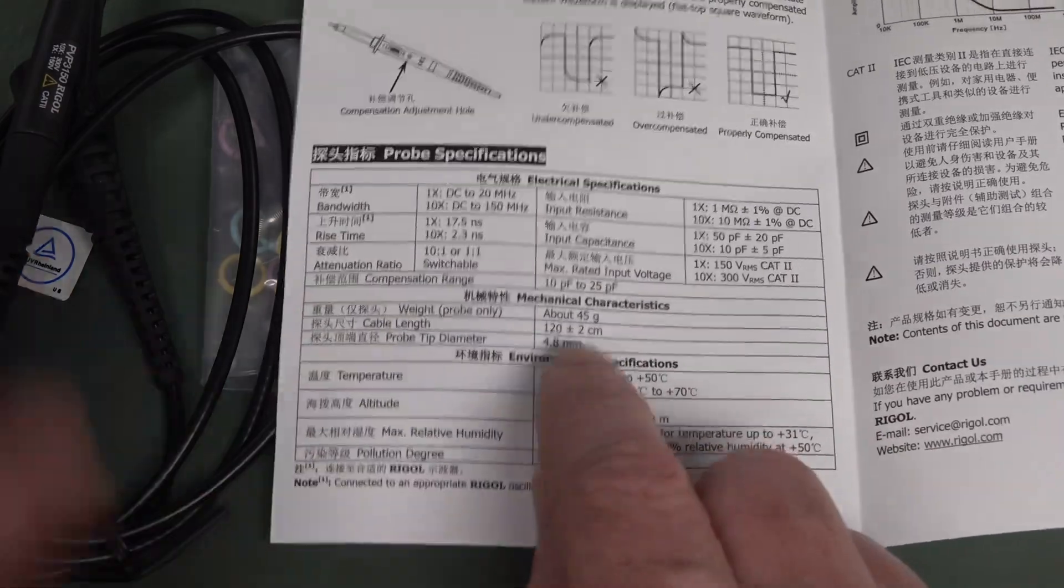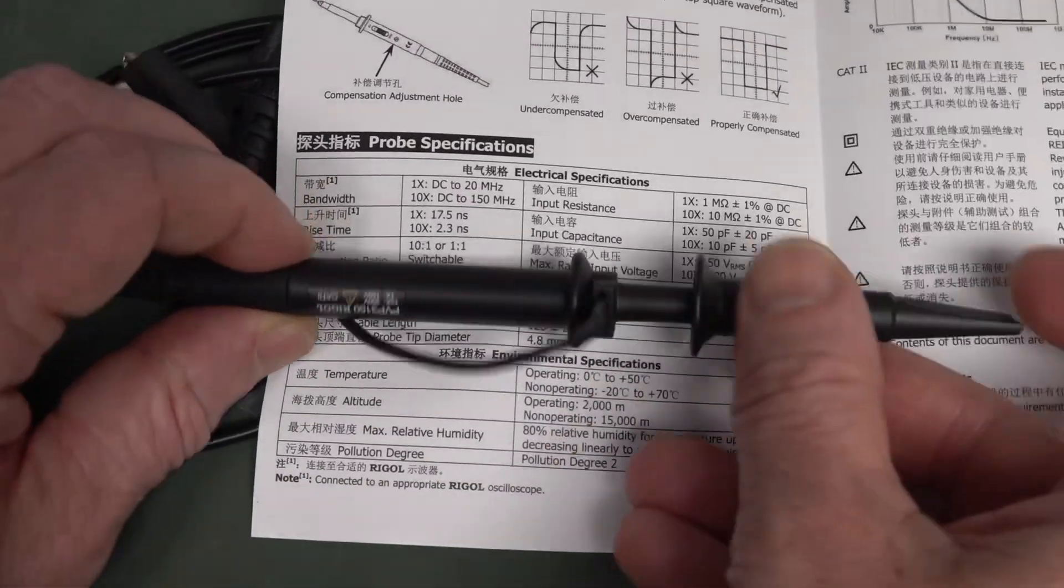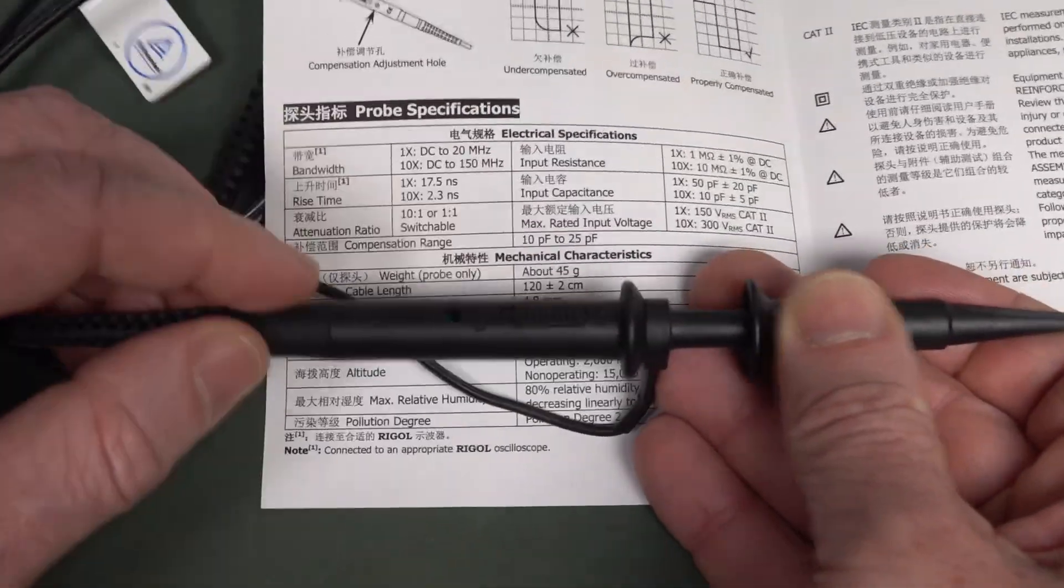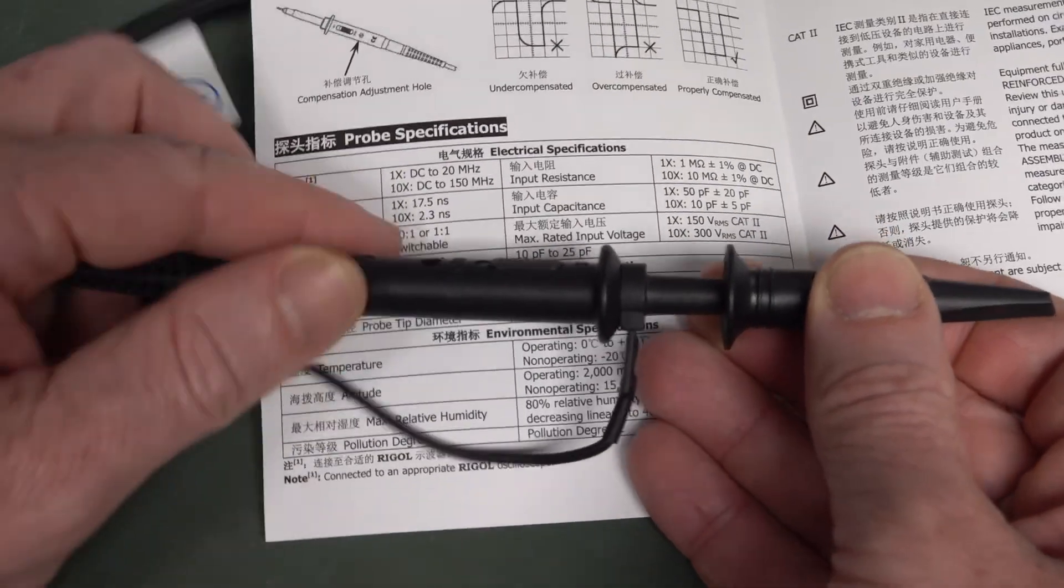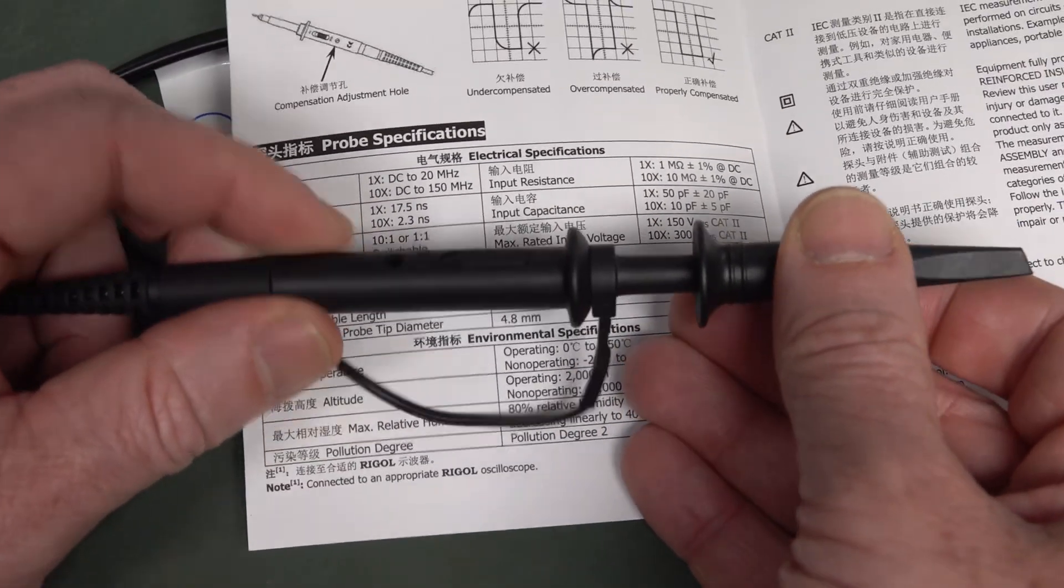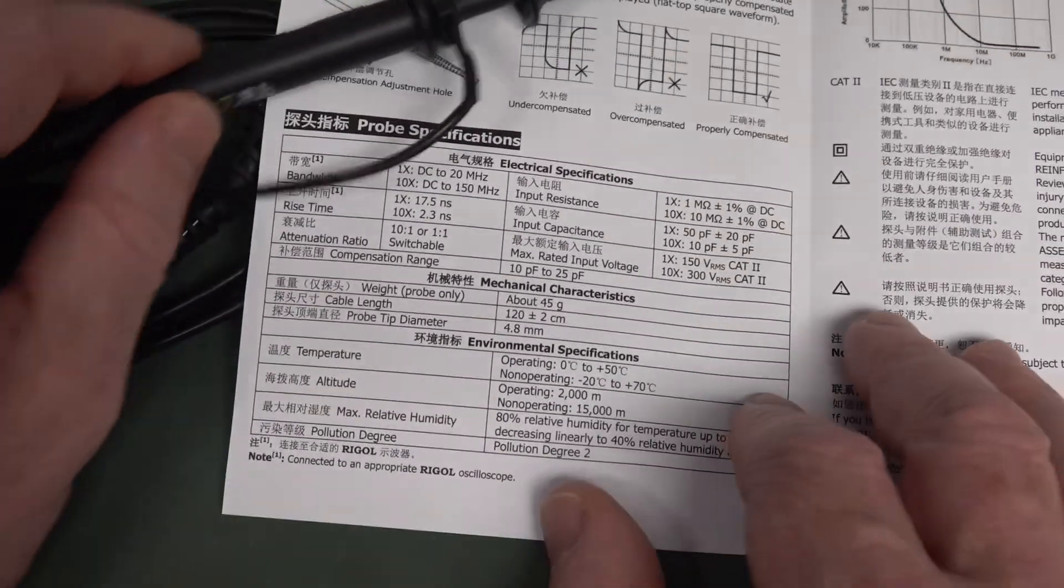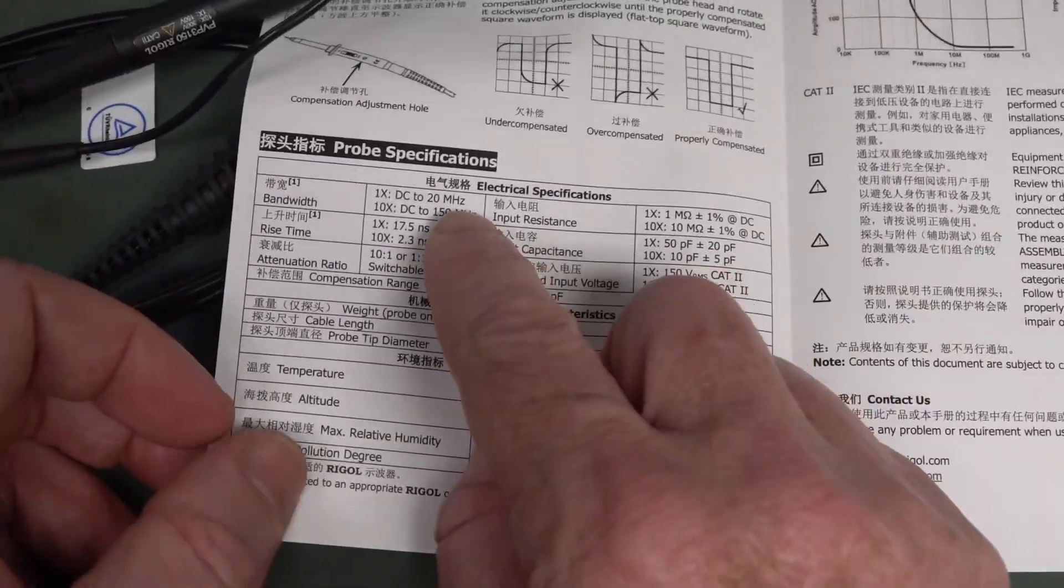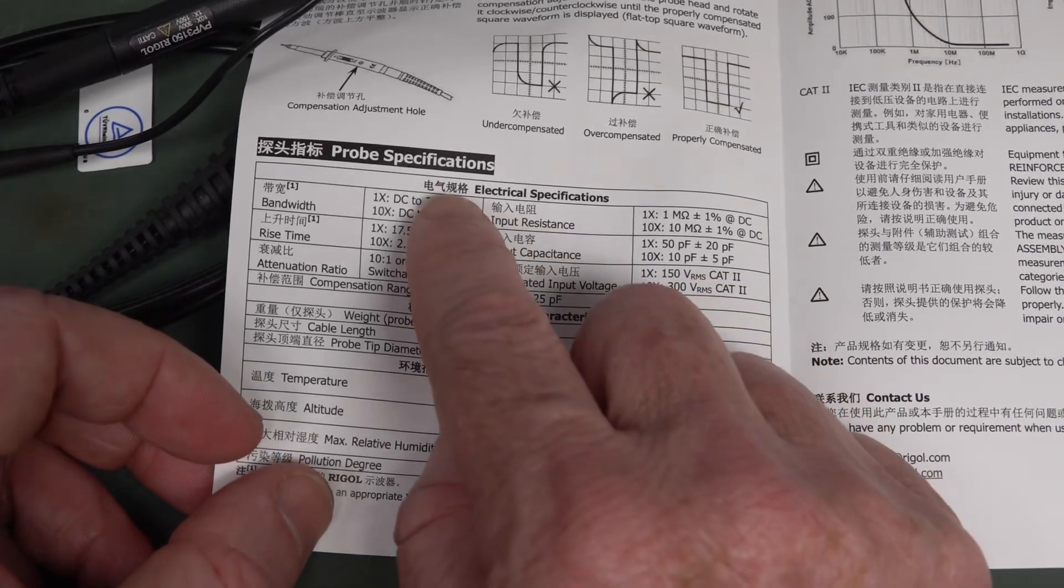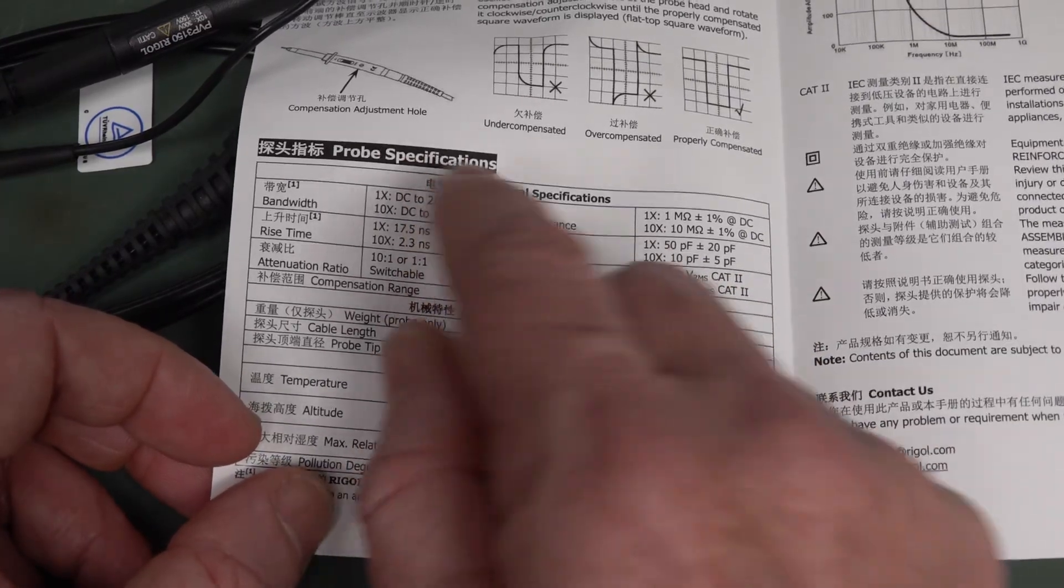Now, that's handy because you often want to use one of the applications for using the x1 position, for example, is measuring noise. And noise is typically measured over a standard bandwidth, just an industry standard, because you have to pick something, of 20 megahertz. And that's why oscilloscopes have 20 megahertz bandwidth limits.